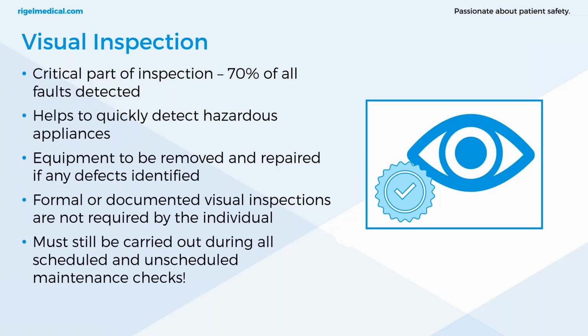So visual inspections of the equipment help to identify any hazardous appliances in the healthcare facility fairly quickly, and they form a critical part of general safety inspections during the functional life of the medical equipment. Around 70% of all faults are detected during this visual inspection. And it's not just the biomeds, the engineers within the hospital. All staff should be expected to be observant of the condition of the equipment that they use, and if faults appear, then that should prompt them to send it to the biomed department for repair and removal of the appliance from service.